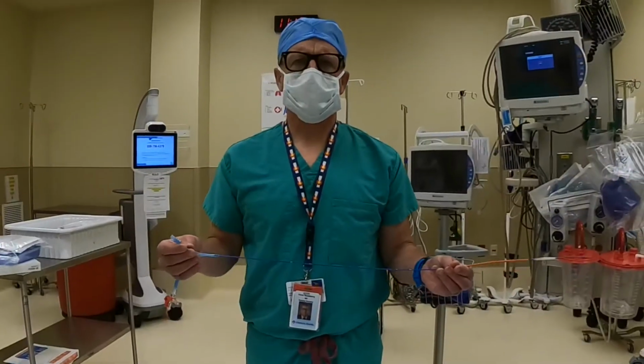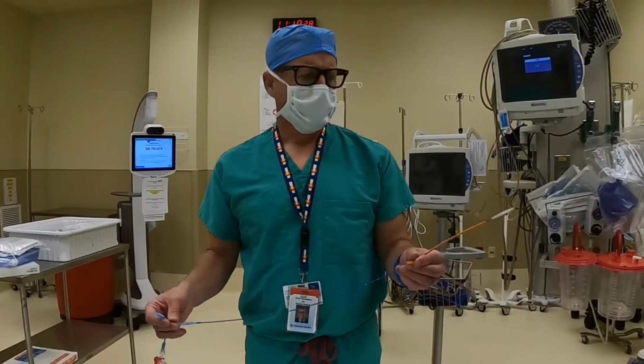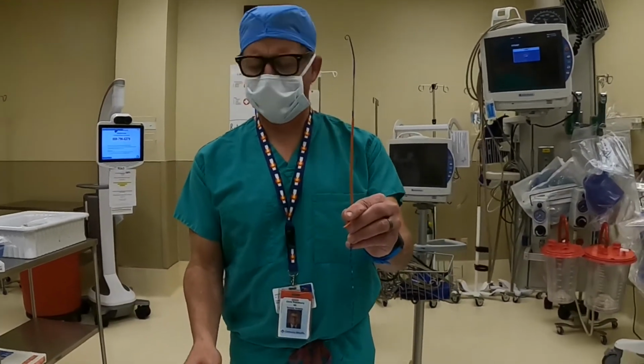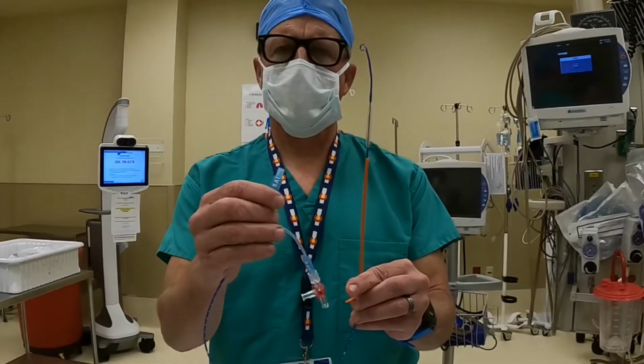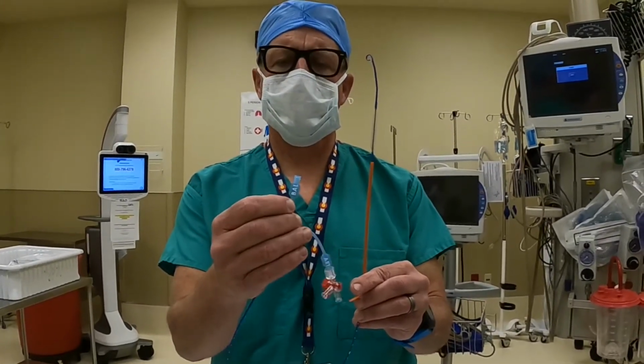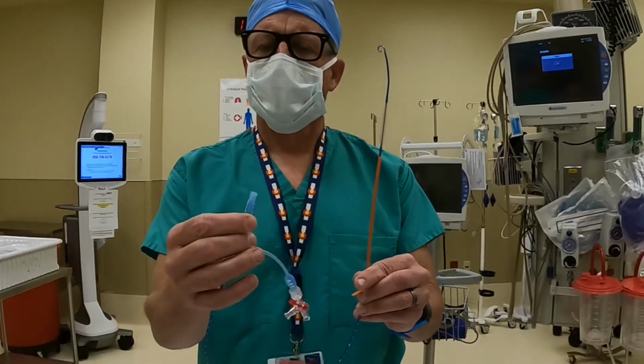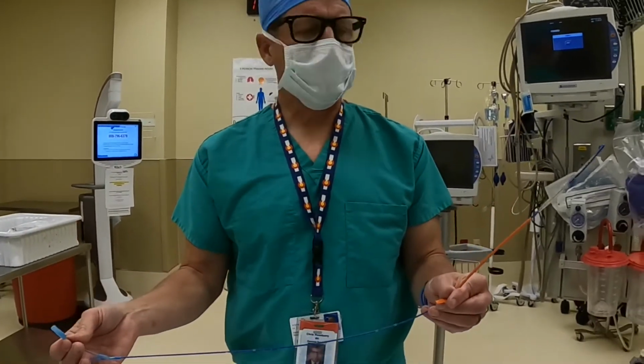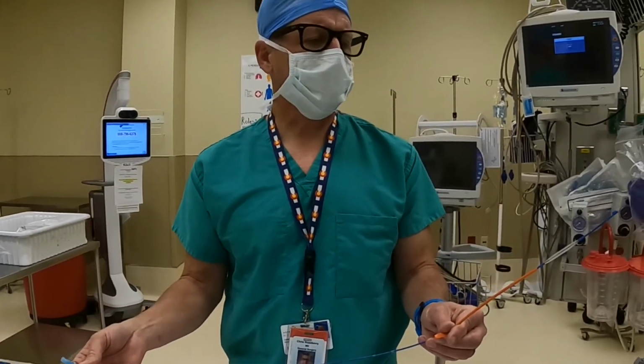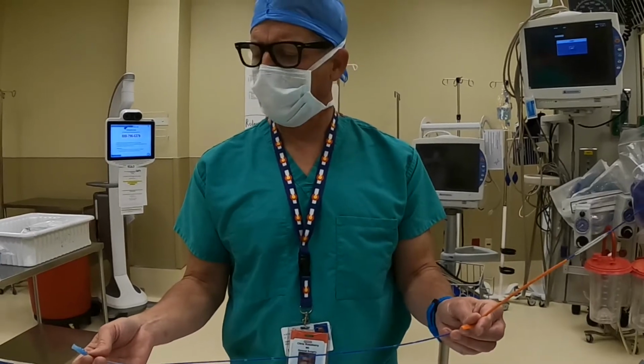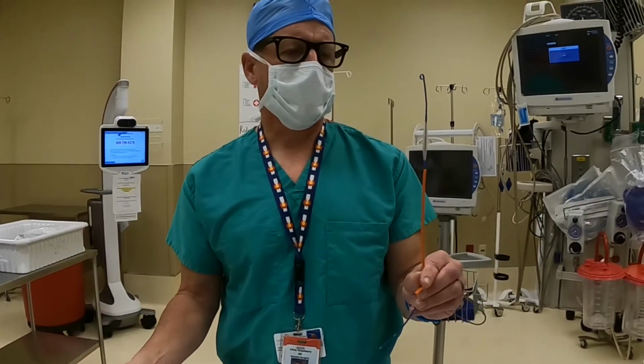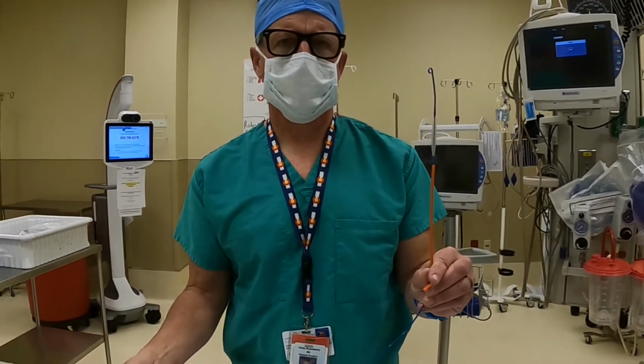The next step is to flush and deflate the balloon. If you look at the catheter, the balloon is exposed, and the balloon port is very visible with a label that says balloon. You'll put your syringe on there with some saline, and you'll flush the balloon and then suck that out and make sure we're back to a completely deflated balloon.